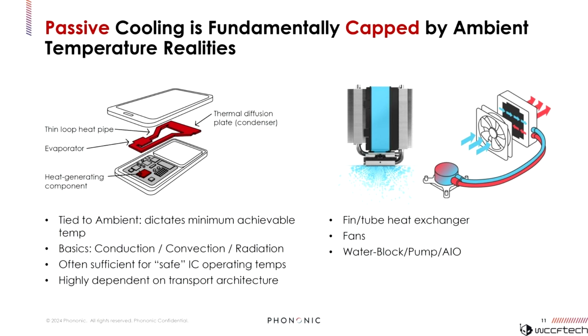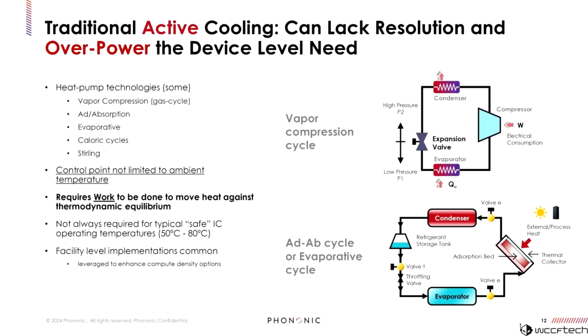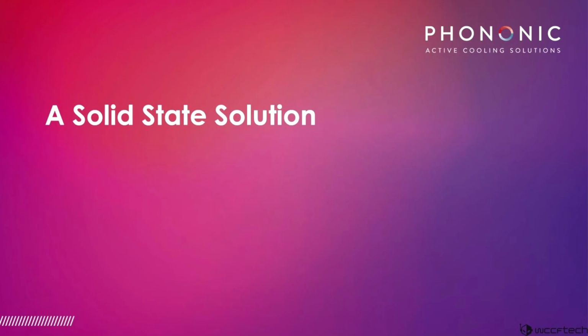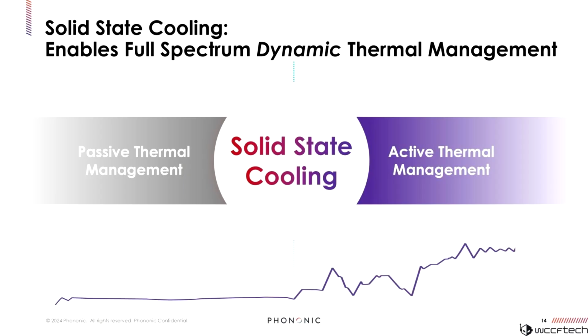Conventional setups currently use either air or liquid cooling. Air cooling is mostly used in passive solutions and is reaching practical limits, driving the need for liquid cooling, as seen in most NVIDIA Blackwell platforms integrating custom liquid loop designs. Passive cooling is capped by ambient temperatures, while active cooling can lack resolution and lead to overpower. Phononic introduces its solid-state cooling solution, which provides both passive and active thermal management.